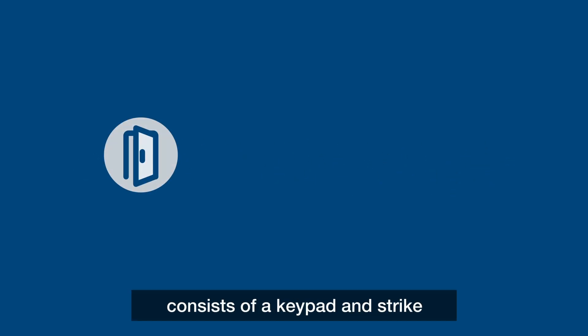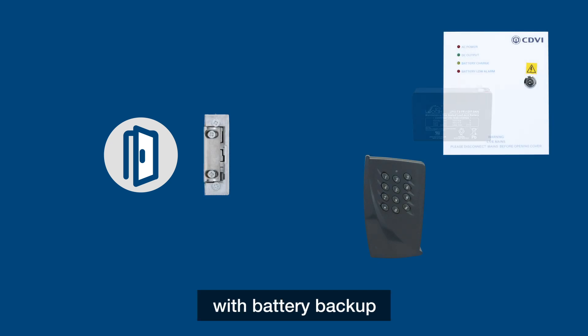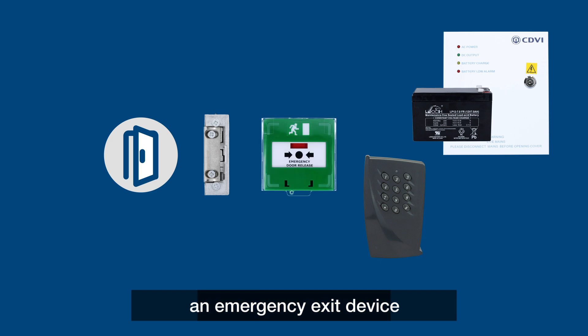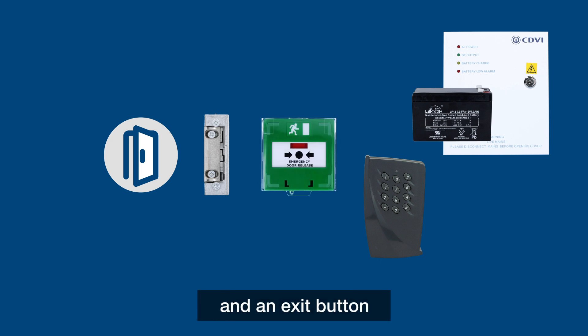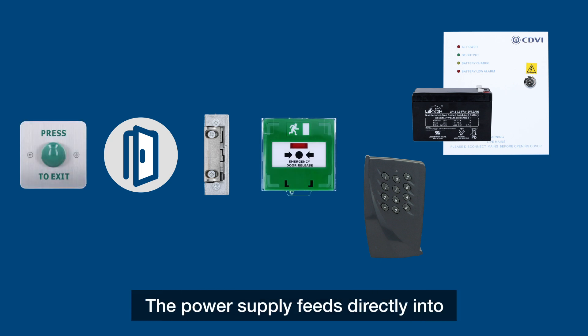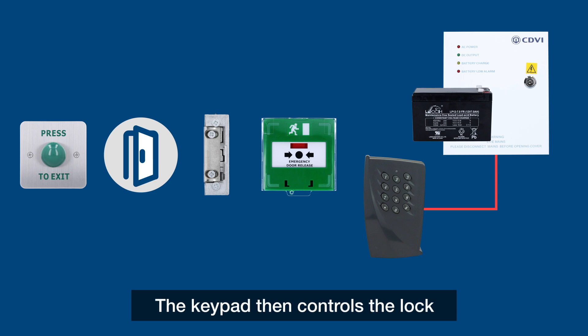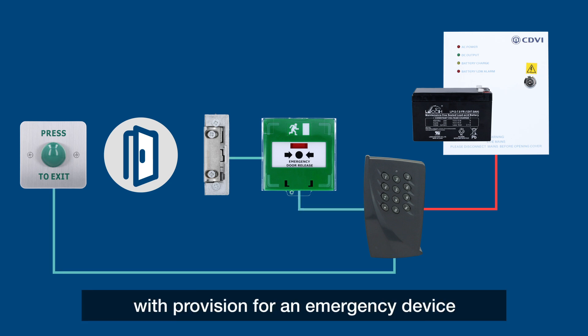One simple configuration of a standalone system consists of a keypad and strike powered by a power supply with battery backup, an emergency exit device, and an exit button. The power supply feeds directly into the keypad and the lock. The keypad then controls the lock through a relay with provision for an emergency device.